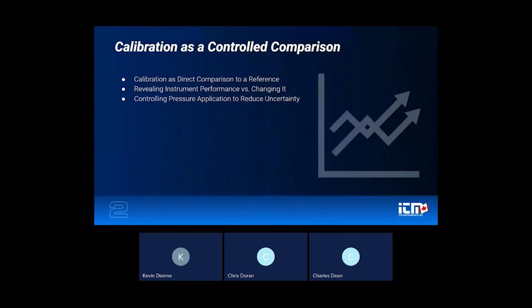So calibration is a controlled comparison. When we talk about calibration, it's important to separate the act of calibration from the tools being used and focus instead on what the process is actually doing. Calibration is fundamentally a comparison. A known pressure is applied and the response of the device under test is compared directly against a reference. The result is a quantified difference at defined test points.